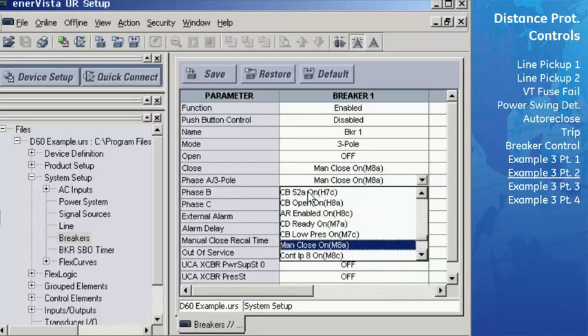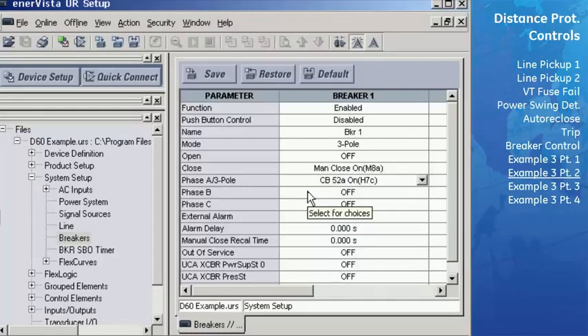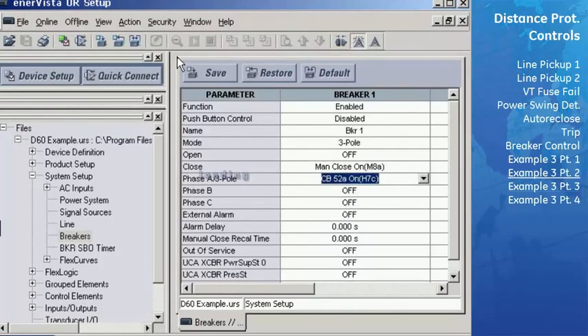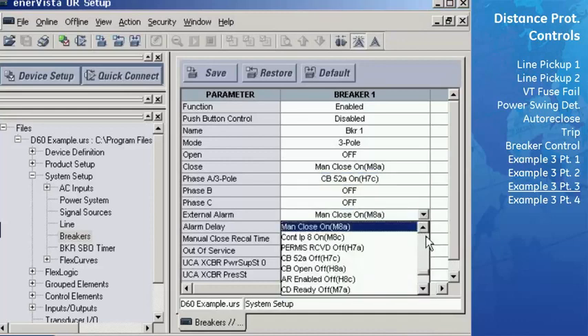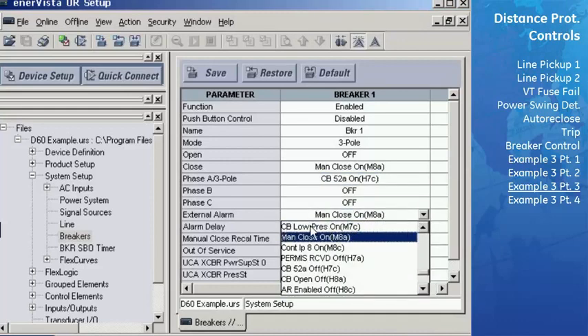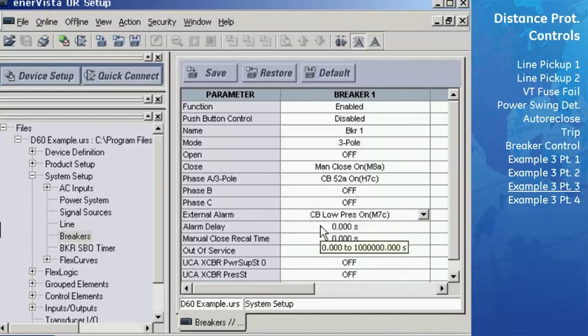Phase B and phase C settings won't be used since we will always be tripping all 3 poles of our breaker. For this example, an external alarm, breaker SF6 low pressure, is wired to contact input M7C. Therefore, set the external alarm field to contact input M7C on. The contact input already has a debounce time of 2 milliseconds, so the alarm delay can be left as 0 seconds. A circuit breaker ready signal is wired to contact input M7A.